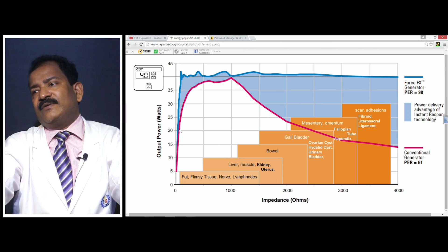Will I tell my nurse to keep on changing the watt from 5, 10, 20, 50 always? No, it is not necessary. You fix the watt, suppose 20, and if you do not want to fix it up or down, you will compensate it by time. Suppose the watt is too much for the tissue which is too soft, I will decrease the time, and if the watt is too less for the tissue which is too tight or too hard, I will increase the time.